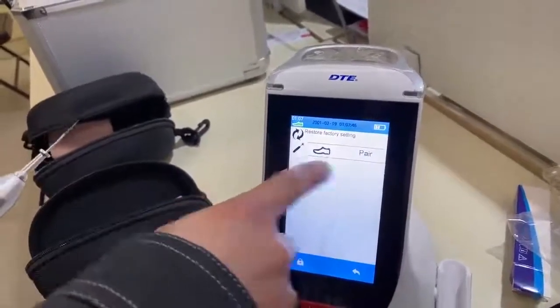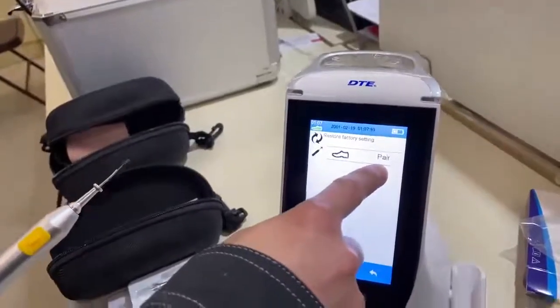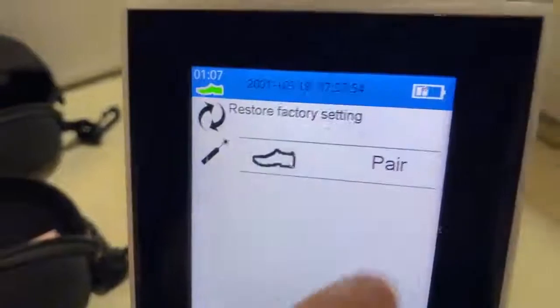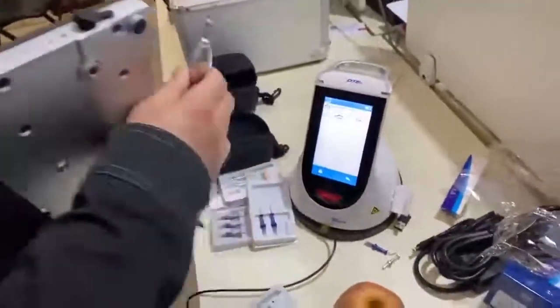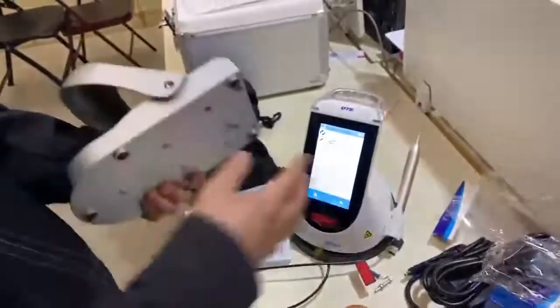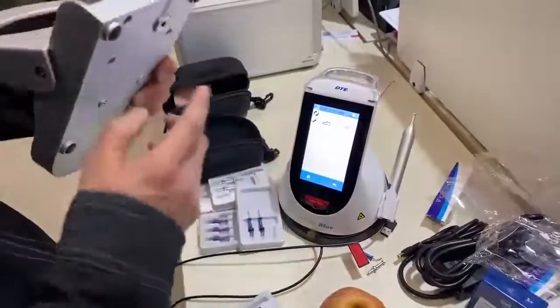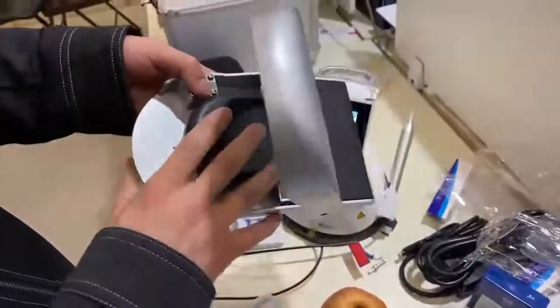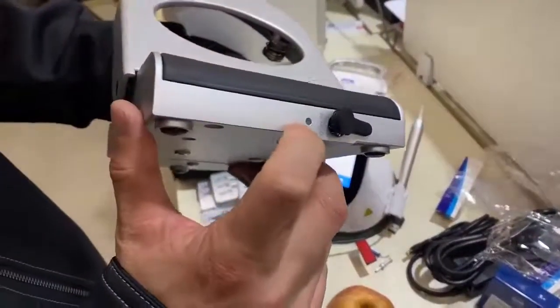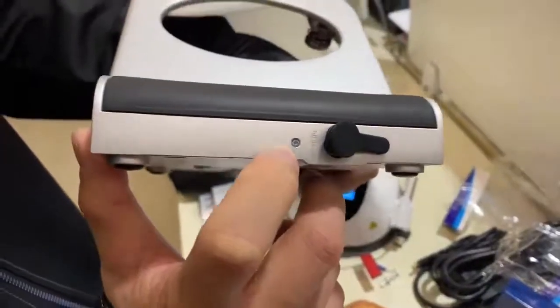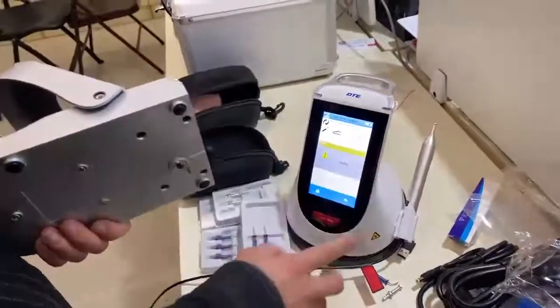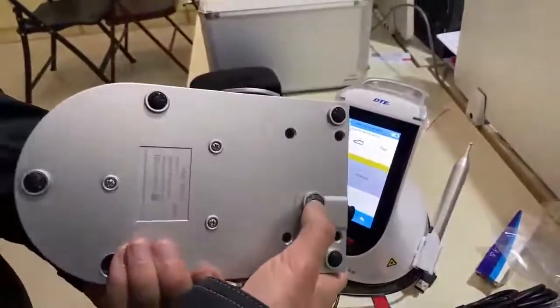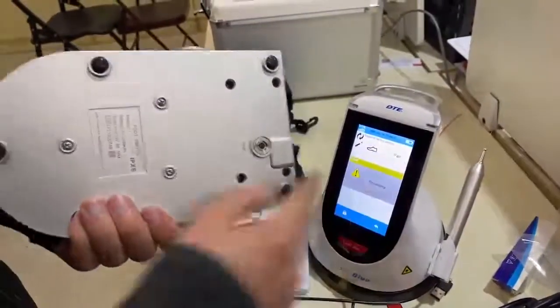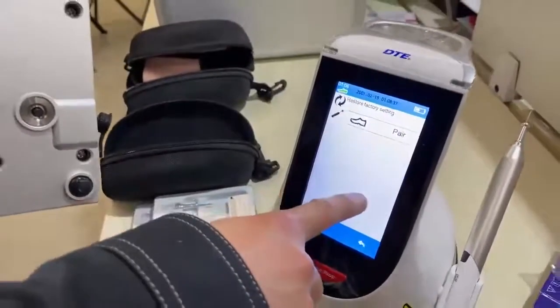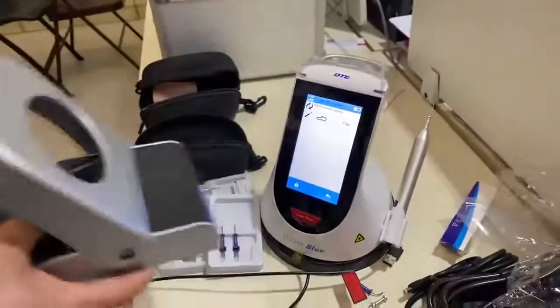And for foot control, you can see we have a pair button here. How can we pair the foot pedal? Remember, only when you have problems with the foot pedal and you replace it with a new one, then you need to pair the new foot pedal with the device. We first press the foot pedal to activate it, and then you can see it will flash the green light. Then you press the pair button, and then press this button for pairing. You can see here, successfully pairing. So this is how we pair the pedal with the device.